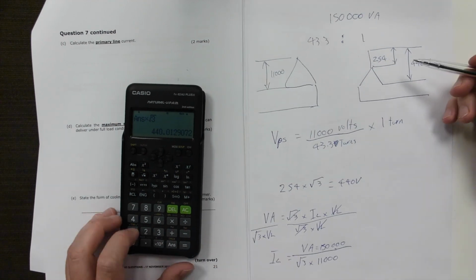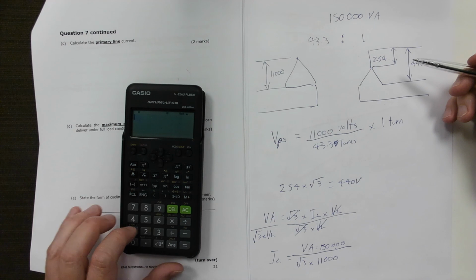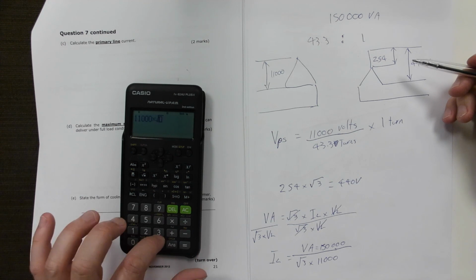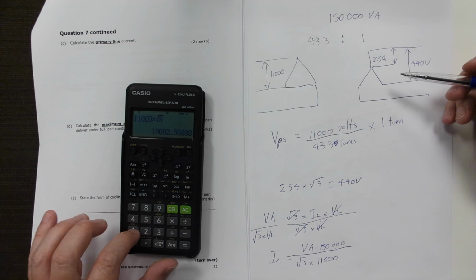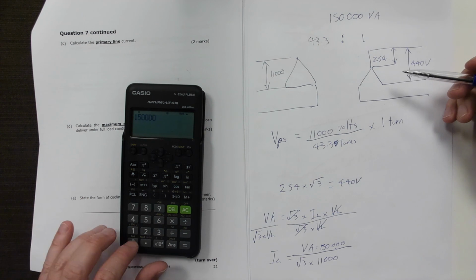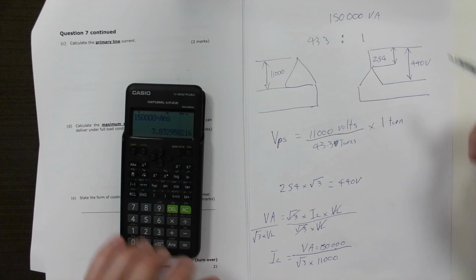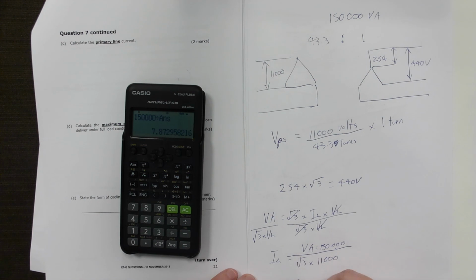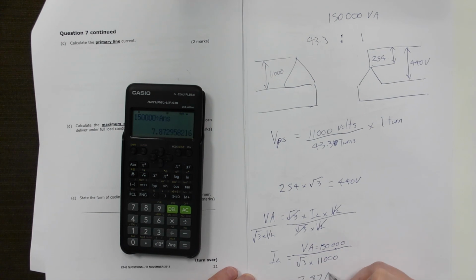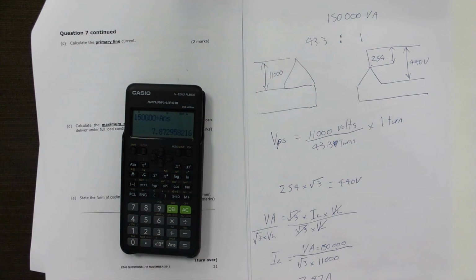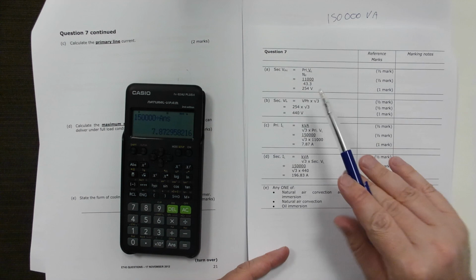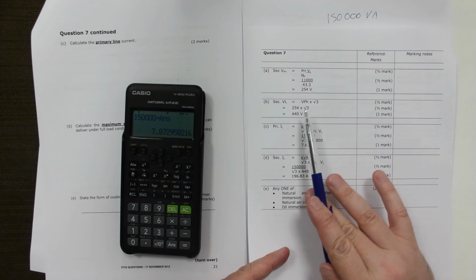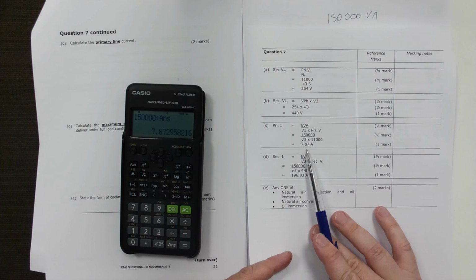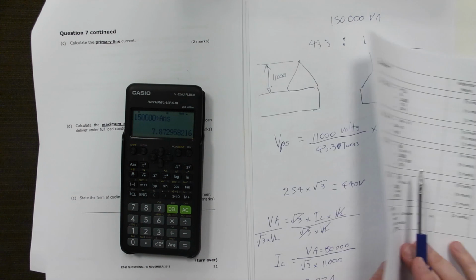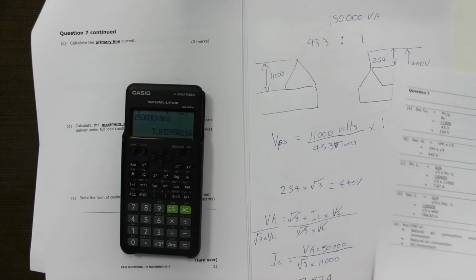So 11,000 times root 3, and then 150,000 divided by answer, and we get 7.87 amps. Because the third digit is a 2, we round down. And if we look at our formula sheet, we can see 254 for the first voltage, 440 for the second voltage, and then 7.87 amps, which matches us so far.